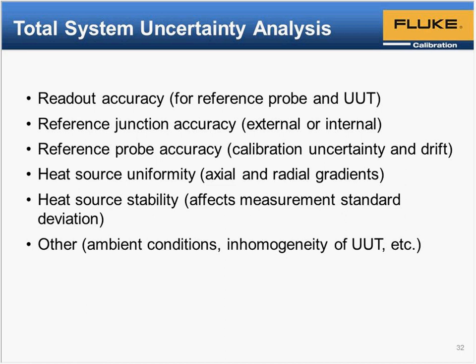Here is basically a standard set of uncertainties that you would consider for a thermocouple calibration system. You have to consider the readout accuracy and the junction accuracy, whether it's the readout's reference junction compensation circuit or your own ice bath. Then uniformity, meaning how consistent the temperature is inside the heat source, and stability, which is seen by taking 30 or 40 readings and looking at the standard deviation to see how stable the readings are. And there are some other sources of uncertainty, like homogeneity, potentially.